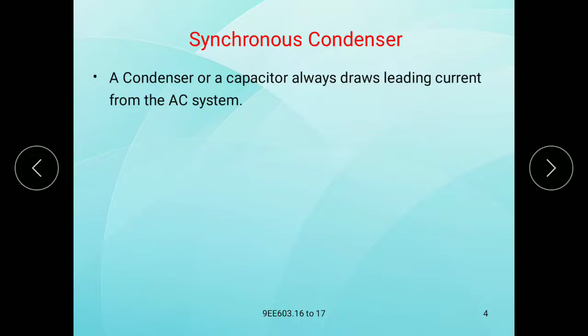Now it is known that a synchronous motor can be operated at unity power factor, lagging power factor, or leading power factor, just by changing the excitation. So by changing the excitation, we can operate in different power factor conditions. The ability of the synchronous motor to operate at leading power factor when overexcited is utilized in improving the power factor of the system. Underline this one: a leading power factor when overexcited is utilized in improving the power factor of the system.